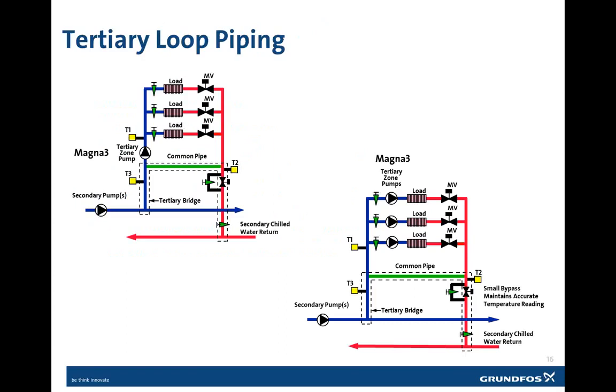And then the secondary pumps are selected just to overcome the friction loss in the distribution piping to and from the central plant, as opposed to also overcoming all the head within the building. So the excess head required to pump to the building due to large loads or high resistance is not imposed upstream or downstream of the building. And then the tertiary pumps are selected for the building load only. So they tend to be a lower horsepower, which is really an ideal application for the Magna 3 and some of the opportunities there.